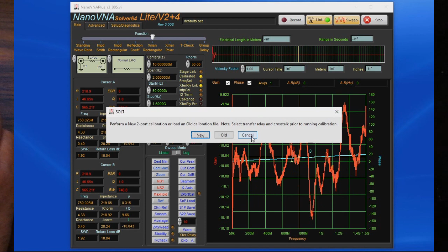I'm going to change our start frequency to 1 megahertz, and I'll change our stop frequency to 6.4 gigahertz. And let's go ahead and we'll run a sweep. Let's turn off the phase. Again, this is supposed to be a 10 dB part, and you can see it's all the way up to about 8.6. It's as low as 15.2 or so dB. So again, is this a problem with the attenuator, or maybe it's just our lack of calibration?